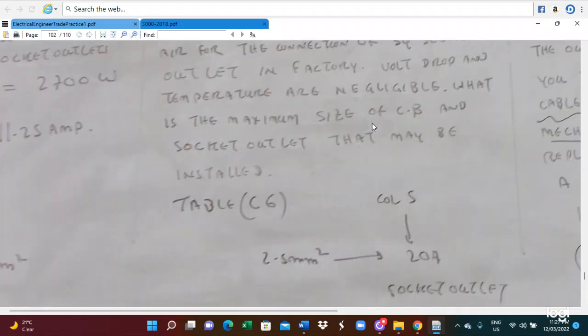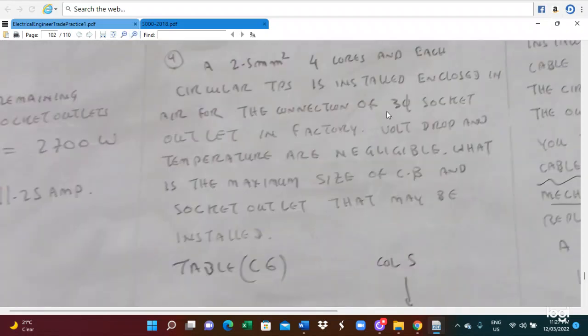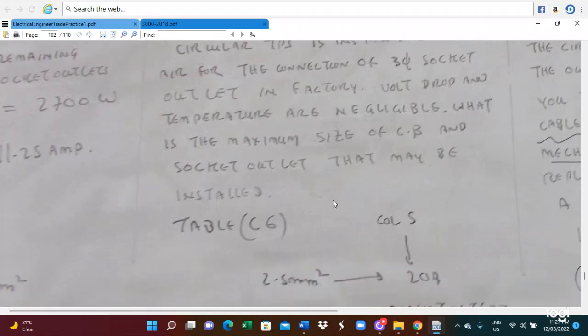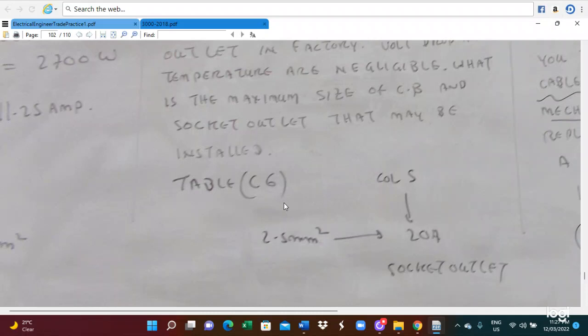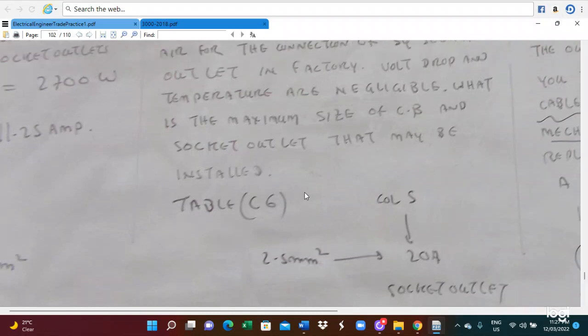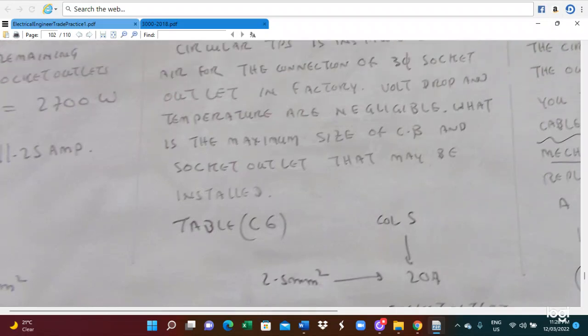The next one is 2.5 millimeter square, 4-core circular TPS cable installed enclosed in air for the connection of a 3-phase socket outlet. In this case, we determine that temperature is negligible. What is the maximum size of circuit breaker? We find table C6, which gives 20 amperes.